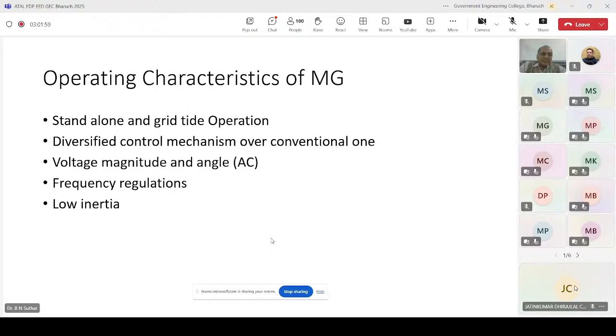The most important characteristic of a microgrid's operation is inertia. If we have a conventional power generating unit, DG, in the microgrid, it's no issue for a conventional power grid because it has sufficient inertia. But when we have RES, like solar, with maximum participation of solar or wind, the inertia is low. We'll discuss its response time in the next slides, and when we talk about microgrid operation, power electronics controls or controllers are more important.